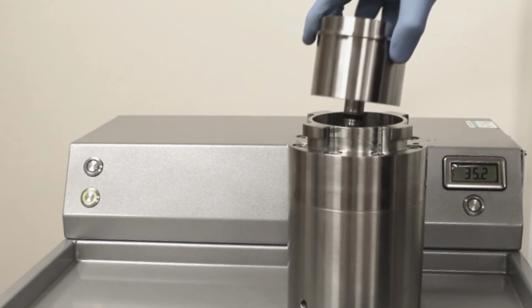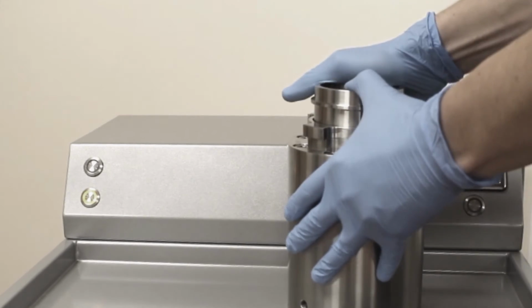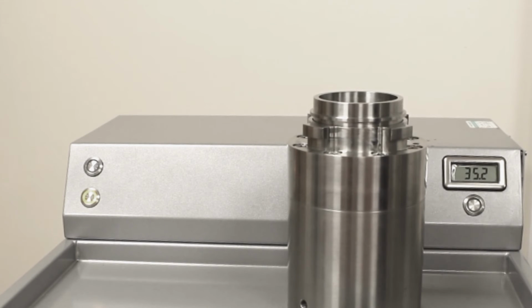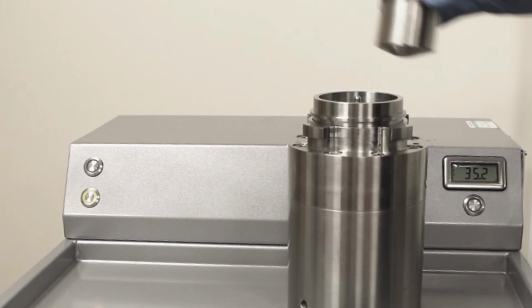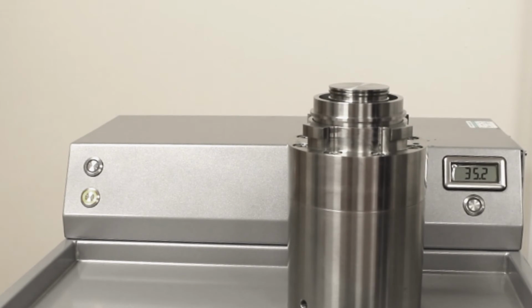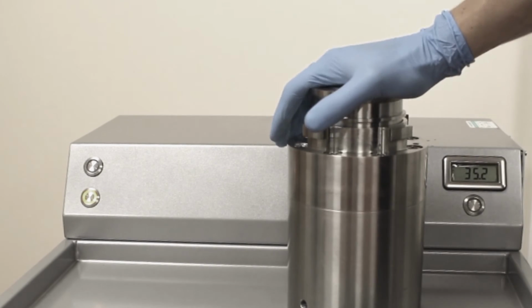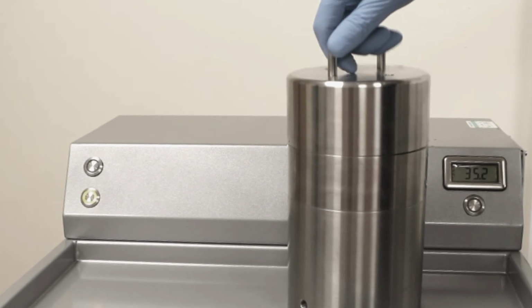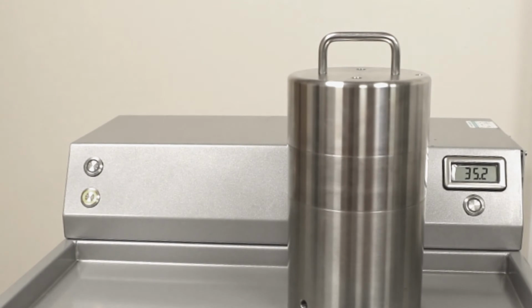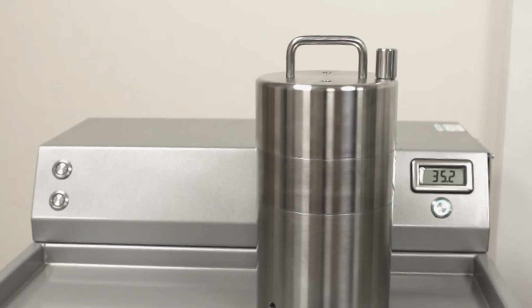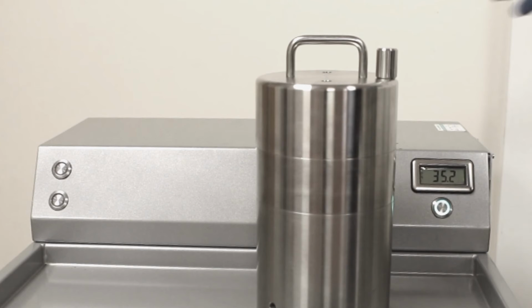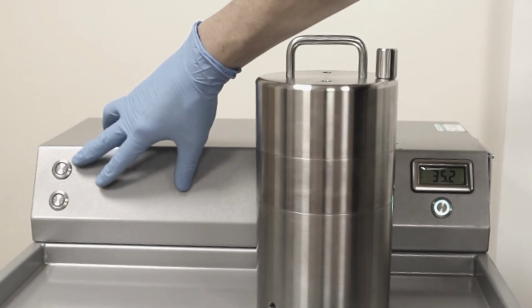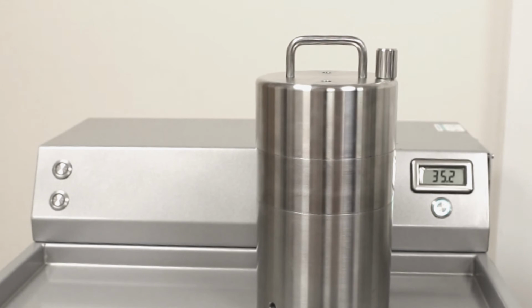Refit the outer cup. The anti-foam pin, the inner cup assembly, the outer cup lid and the main lid. You may have to change the jet if it becomes blocked. The symptoms of a blocked jet are the machine not stroking and your sample not being processed. When the machine is running and neither of these lights are illuminated, that signifies a blocked jet.